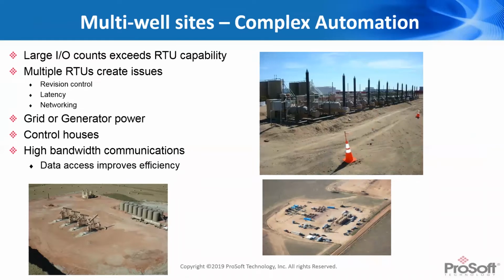With multi-well pad sites, the amount of I/O required at some of these larger sites really exceeds the capability of what a traditional RTU or flow computer provides. For something above a 6 or 12-well pad, you're looking at 3 to 5 or 7 different RTUs just to handle the I/O as well as the measurement functions with standalone flow computers.